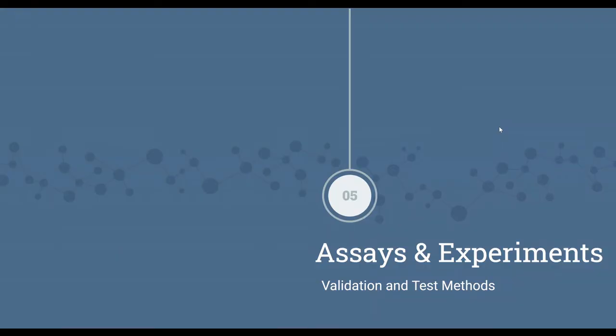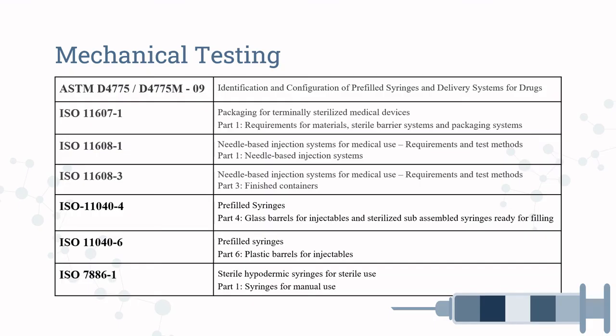Next, we will outline the assays and experiments to be conducted in the testing process of our device. There are numerous mechanical and functional tests that need to be run to ensure that our device is safe to be used in patients. For this device, a wide range of functional testing will be done to validate the appropriate release of clonazepam. It is also important to run impact testing on the drug delivery device. This is done to ensure that the device is not compromised during a seizure where it may be hit. Additionally, mechanical testing should be done on the biosensor to ensure that it can withstand manipulation by the surgeon during implantation. The ASTM and ISO standards that are outlined in the table will be followed to test our device. They will allow us to test for injection time, leakage, non-coring, needle shield removal force, needle penetration force, extreme optimum conditions, and extractables and leachables.